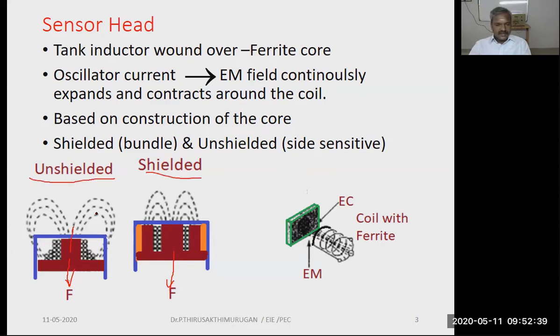So what are the parts of this? It is the electromagnetic field generated by the sensor head. So the winding is wound around the ferrite core. The ferrite core is this shape. Here, this is all winding. This is winding. This is shield. This is the difference between unshielded and shielded. This is shield. Okay, shield. So this is the magnetic field generated by the sensor head. Okay, so we can take the wire from this for lead connections. So two wires for lead connections. So lead wires. Similarly, here we can take two lead wires from the coil.